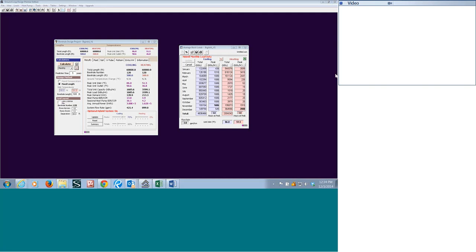Hi, Terry. Just a quick question. Regarding control strategy, obviously in this scenario, let's say you've peaked 50% or 70%, obviously, I think you mentioned that it was a primary, secondary system. So would you basically go to the ground with a VFD when the temperatures are mild and then ramp up your VFD up to, let's say, 90 degrees, and then once the entering water temperature from the loop gets to 90, then you kick in your auxiliary?